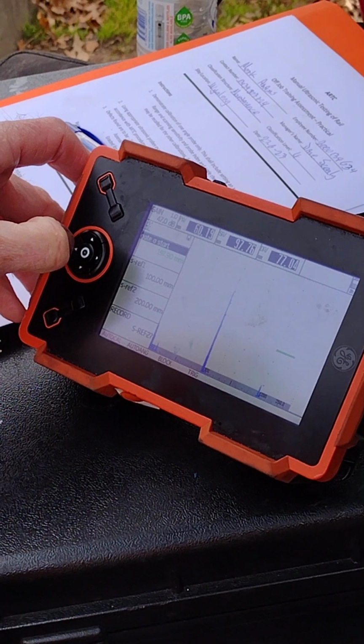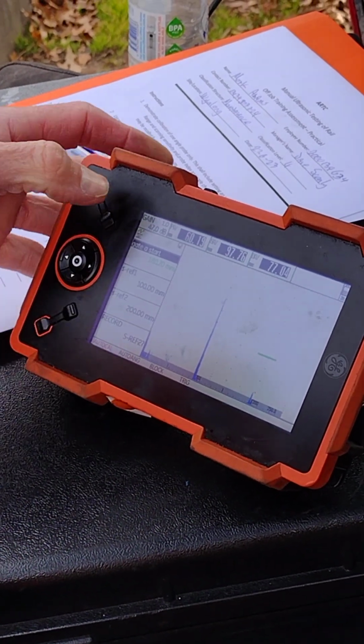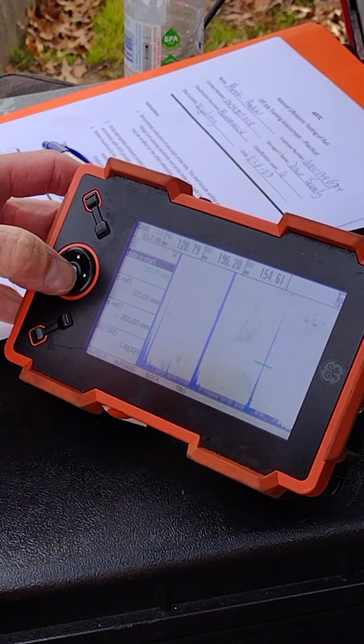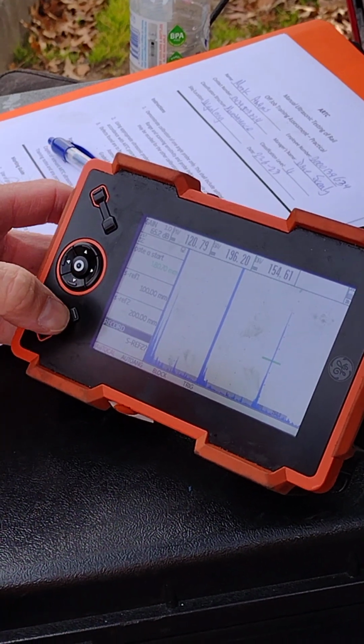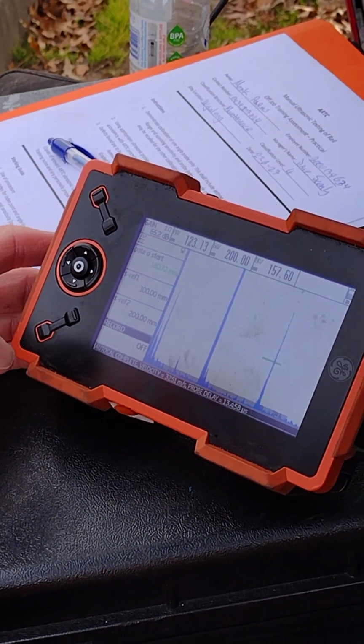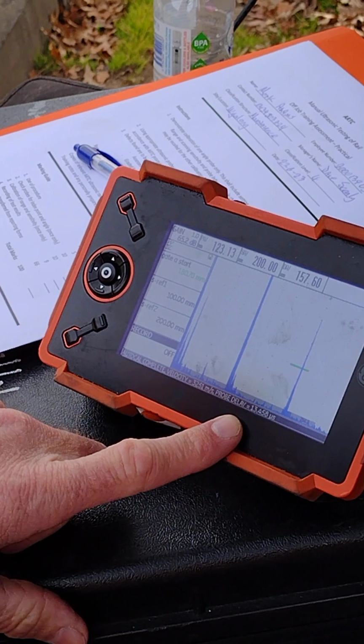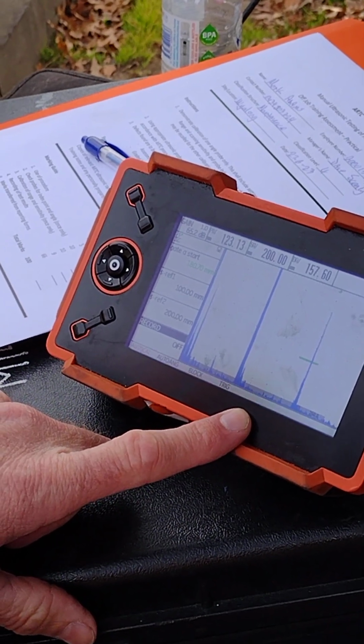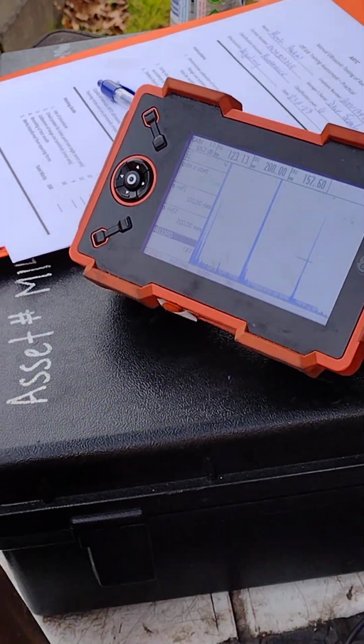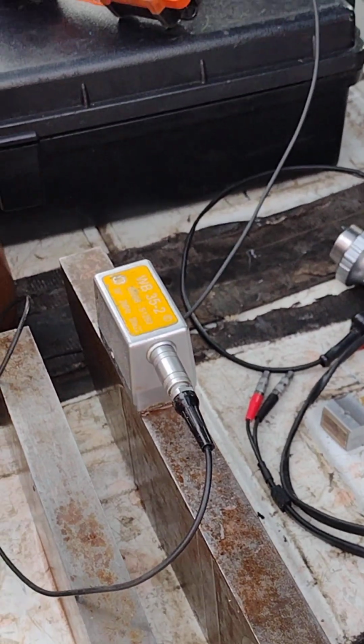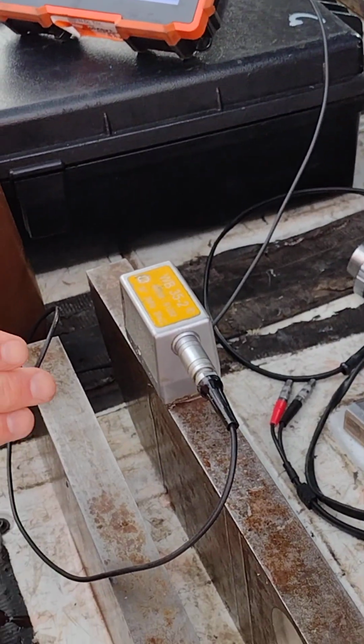We'll then auto, without touching the probe on the job, we're going to auto 80 that peak. We're then going to come down and record S reference 2, and we've got a message telling us that our probe is calibrated. So now we've got our calibration complete, and we've got our index point complete.